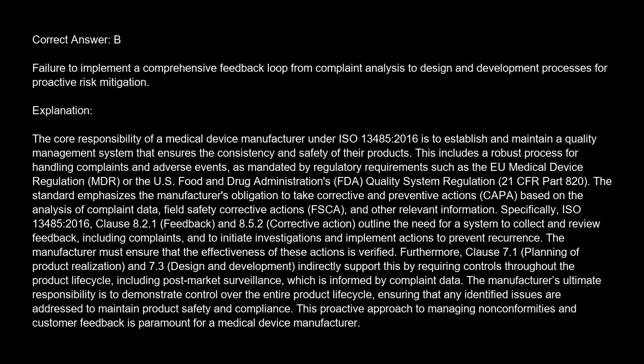Specifically, ISO 13485:2016 Clause 8.2.1 Feedback and 8.5.2 Corrective Action outline the need for a system to collect and review feedback, including complaints, and to initiate investigations and implement actions to prevent recurrence. The manufacturer must ensure that the effectiveness of these actions is verified.